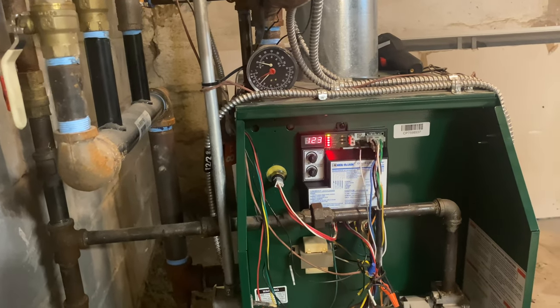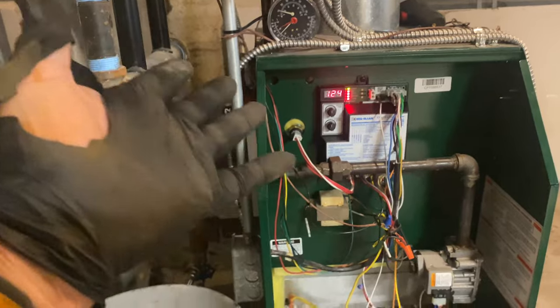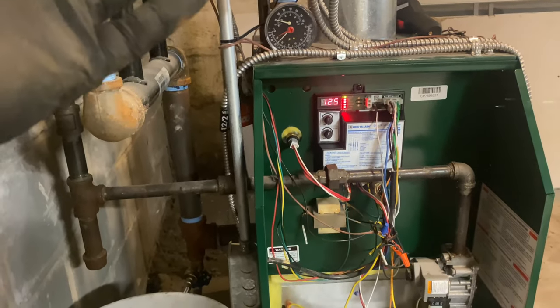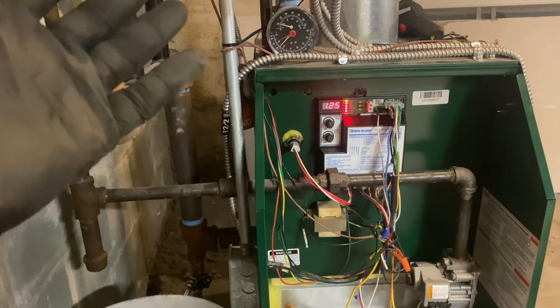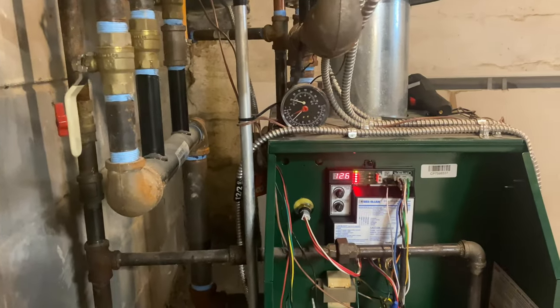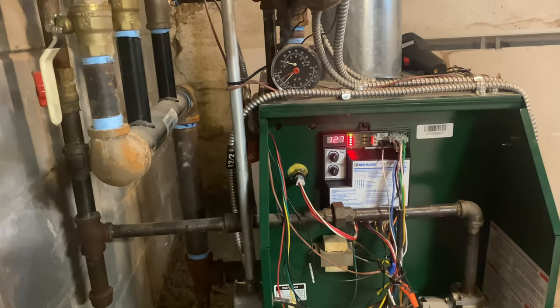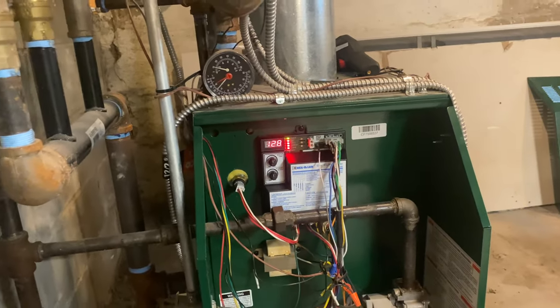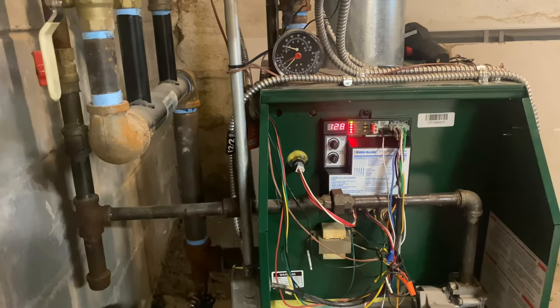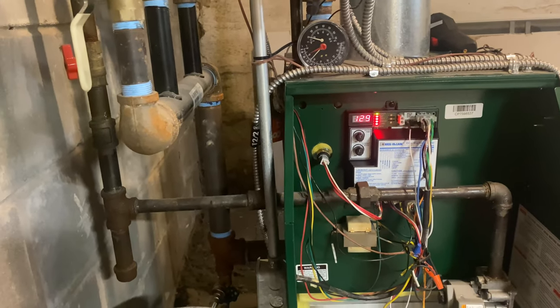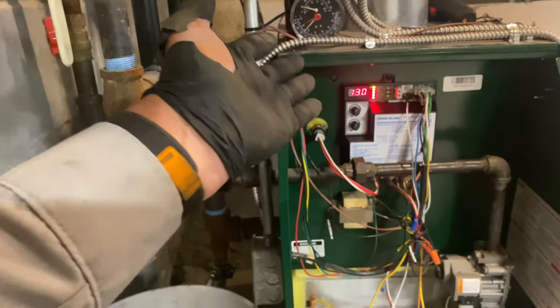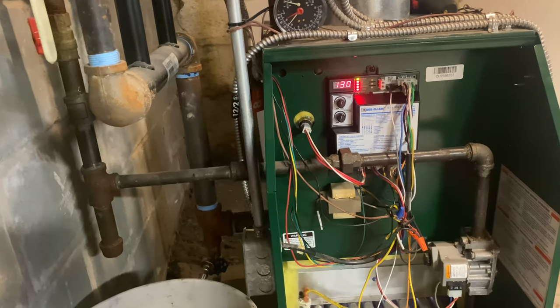They said on those cold days, they felt warmish, the baseboards in the house felt warmish, but it was still 48.5 degrees in the house. That back room was probably 120 degrees, but that radiant room was warm, right? Because radiant heat, in-floor radiant hydronic heating, is designed for 120 degrees, which is what it was running at. So the rest of the house was suffering, right?